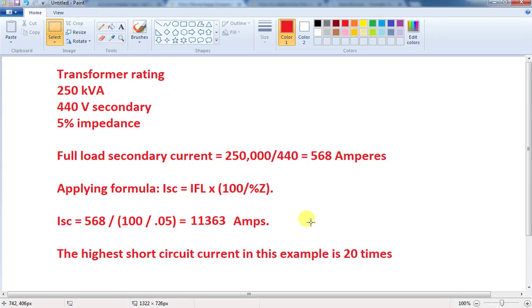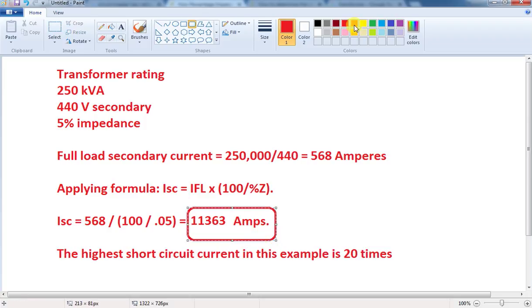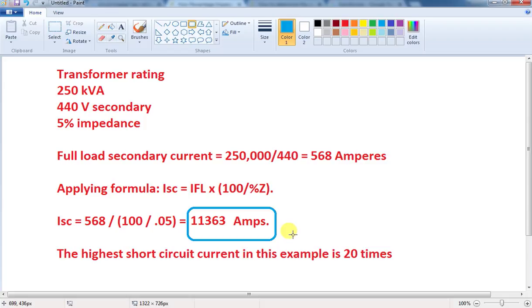Now we have a short circuit current of 11kA. We need to select a breaker. The withstand capacity — that is, the kAIC rating — of that breaker must be at least 11,363A. That is the rating. The percentage impedance is used to limit the short circuit current, and at the same time it helps you design and select the correct breaker.